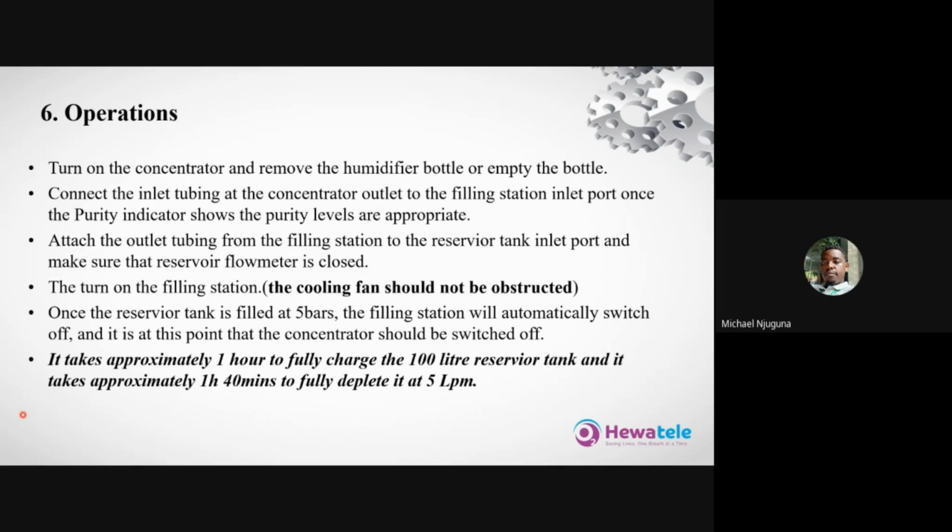Once you turn on the filling station, the cooling fan should not be obstructed. Of course, you would be compromising the cooling effect that is required while in operation. Once the reservoir tank is filled to 5 bars, the filling station will automatically switch off, because of the pressure switch that we mentioned much earlier.